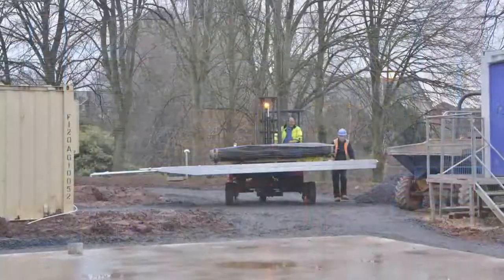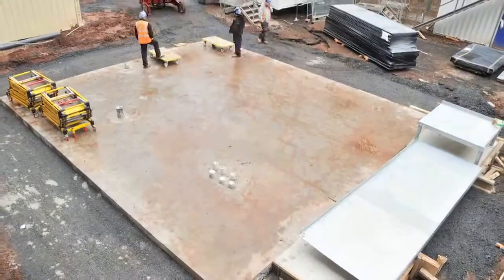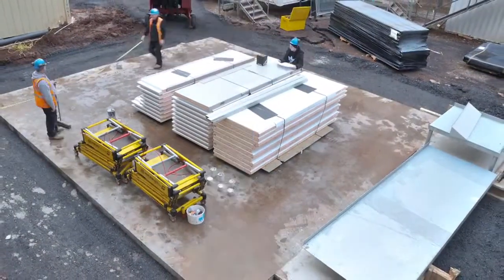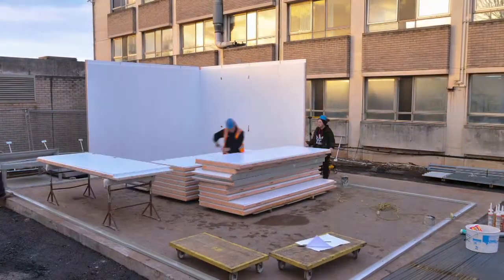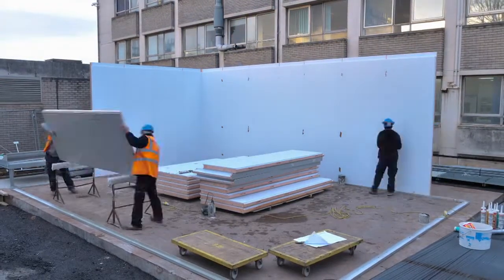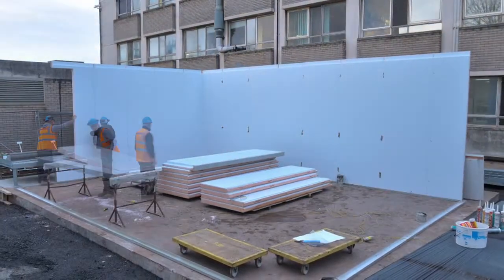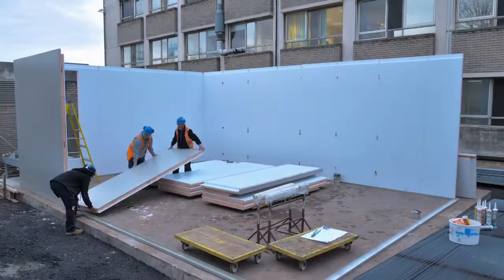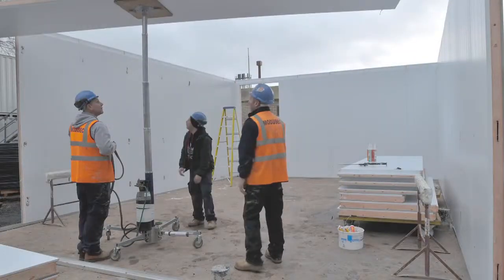Our unique panels are made from pyrofoam phenolic resin bonded between two steel sheets. This means that they are light and strong with a 90-minute fireproof rating. Multiple cam locks built into the panel lock them tightly together to provide a hermetic seal and a high security rating. As well as providing a secure barrier, the panels have a very low U value of 0.18, which means that they are excellent insulators. This reduces the thermal gain on a hot day and reduces the energy required to cool the room, improving energy efficiency.